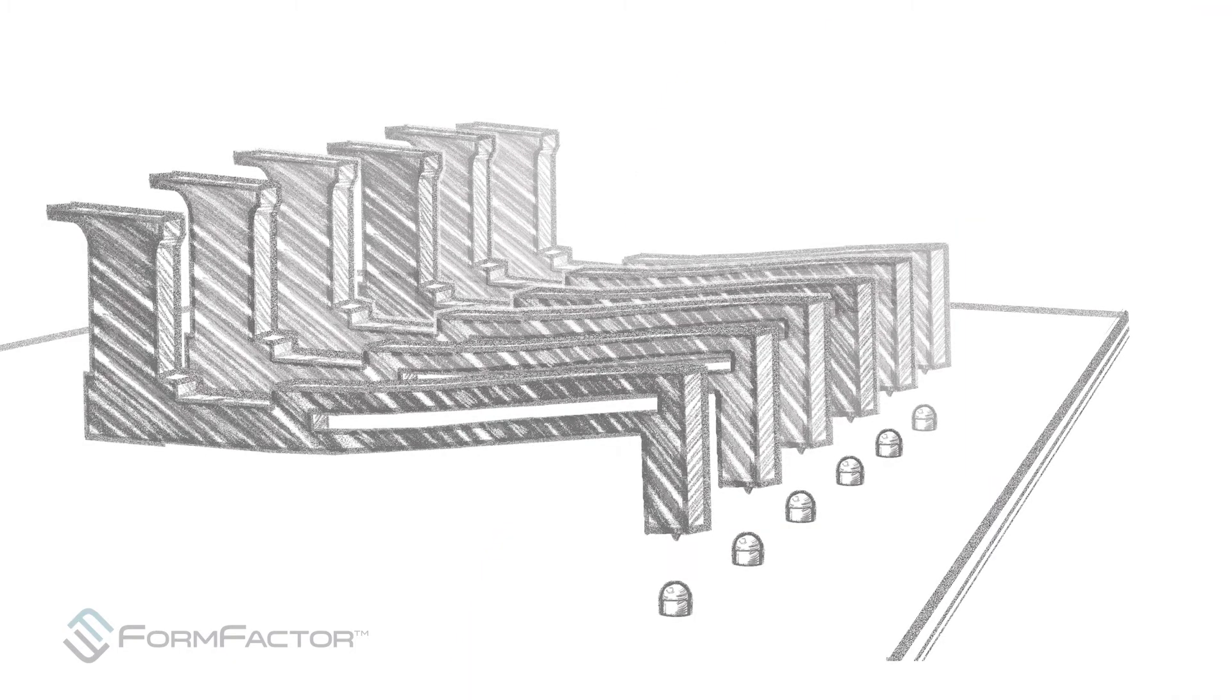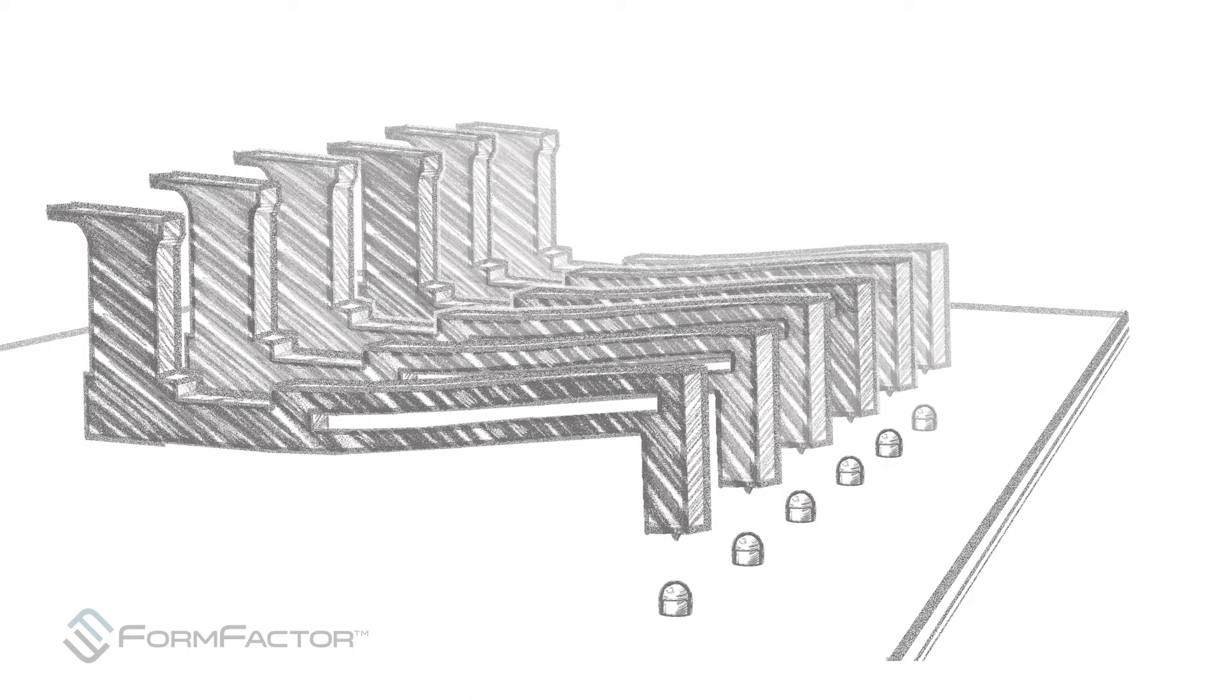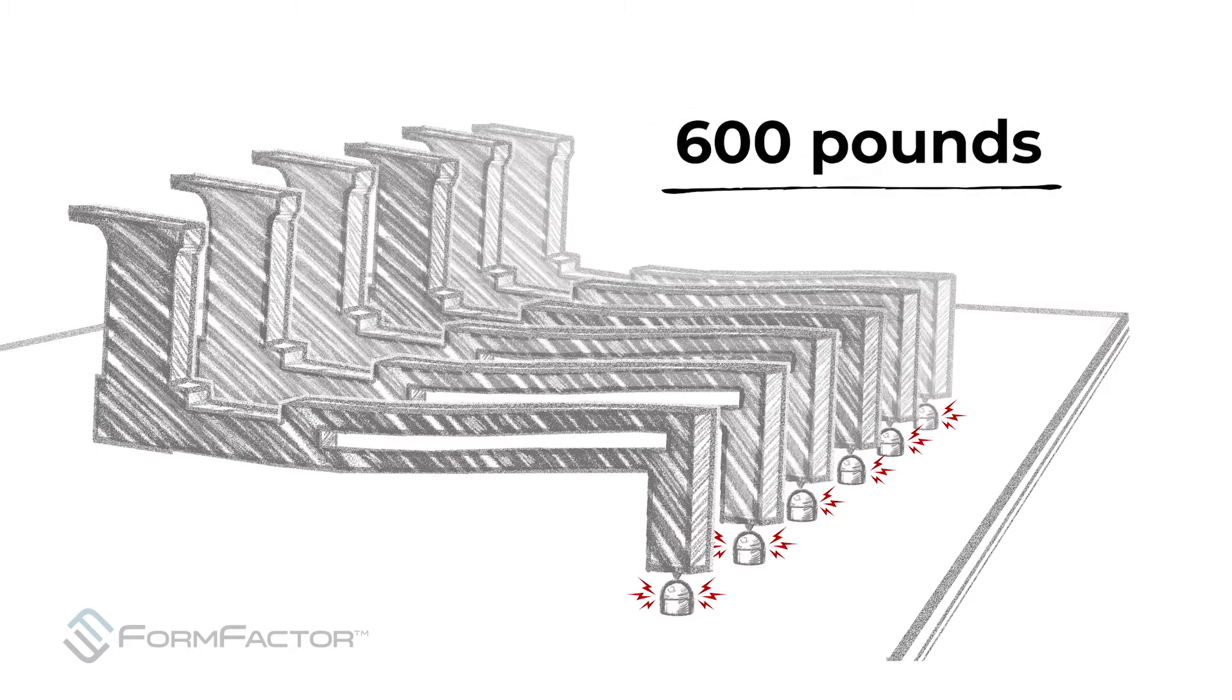To ensure a solid connection, the probes come down on these contact points with up to 600 pounds of force. Think of a vending machine coming to rest on a pane of window glass.